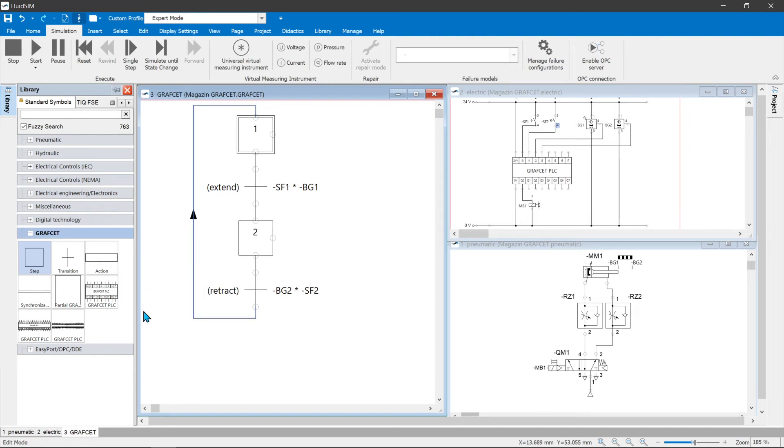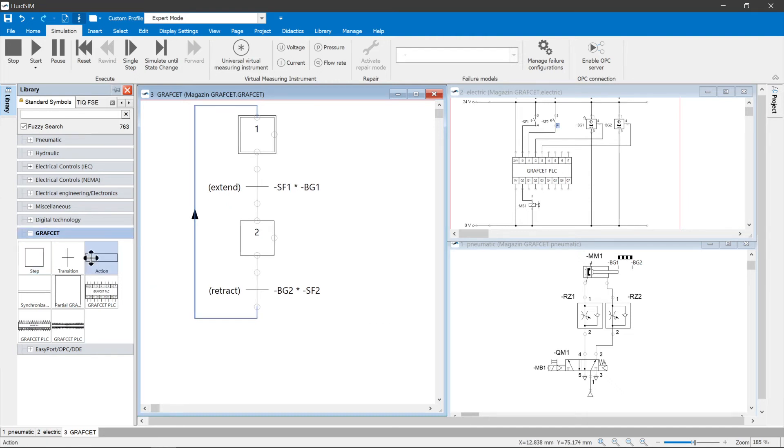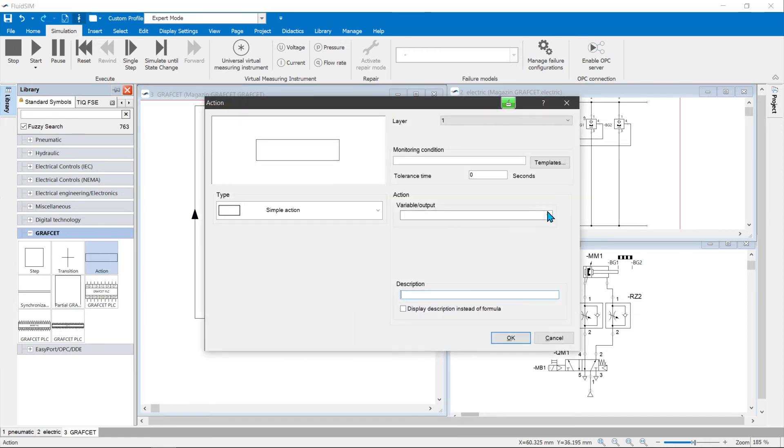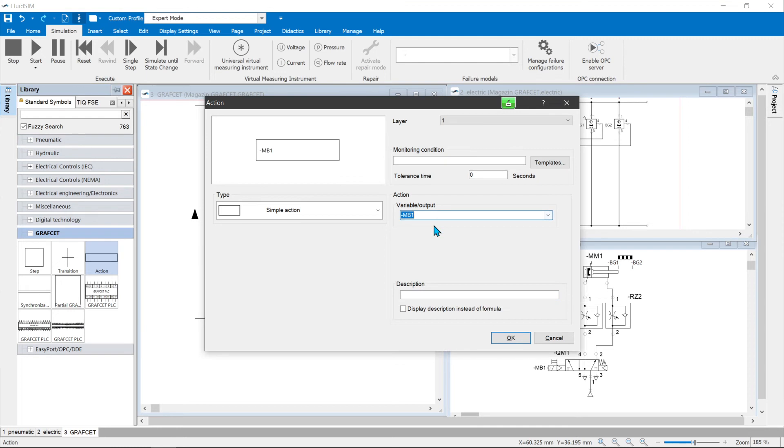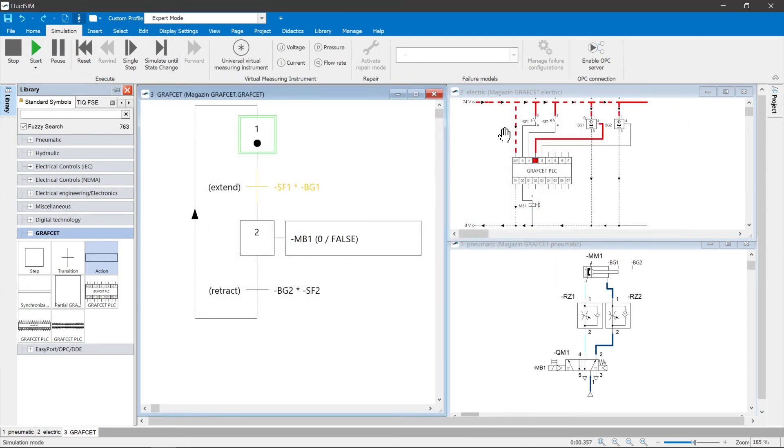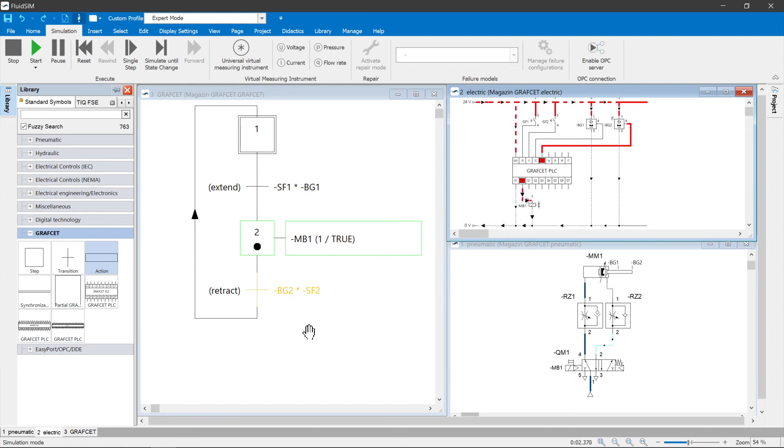The drive has a monostable 5/2-way solenoid valve. If a continuously acting action is connected in step 2 that activates the coil MB1, the cylinder is extended as long as step 2 is active. The GRAFCET thus fully describes the desired sequence.